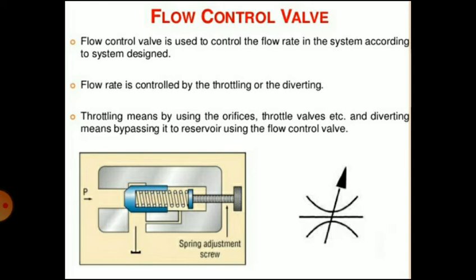If the flow at the actuator inlet is controlled, the circuit is said to be a meter-in circuit. If the actuator outlet is controlled, it is called a meter-out circuit. And when the diverted part of fluid is controlled, it is said to be a bleed-off circuit.